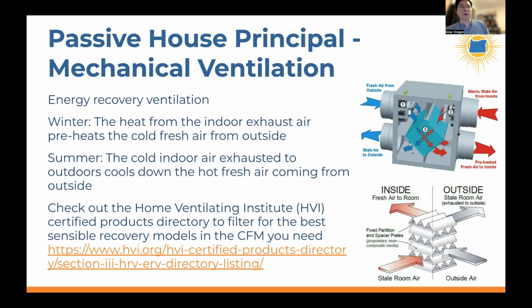How energy recovery ventilation works: the outgoing air in wintertime is warm, and the outside air coming in is cold. In this heat recovery core, there are layers of plastic at right angles to each other - the kind of plastic that, when you hold it in your hand, looks like those campaign yard signs.